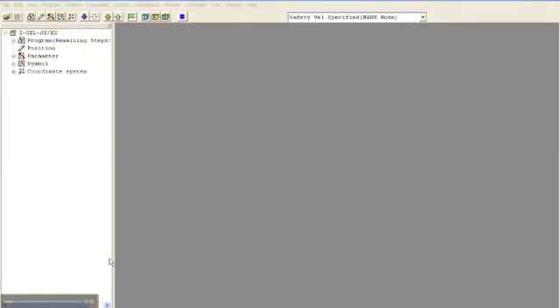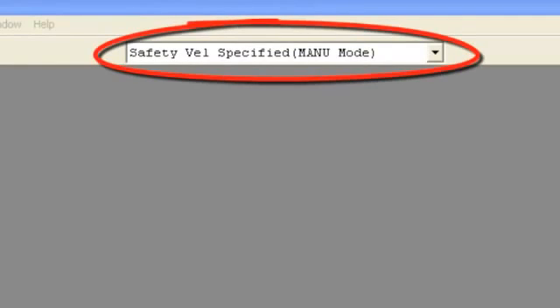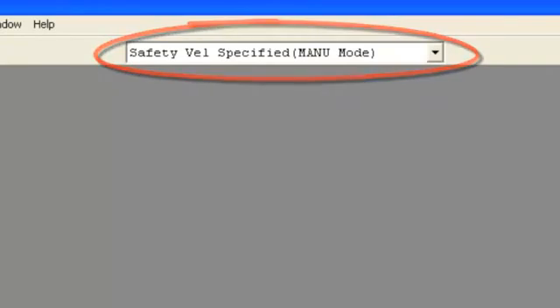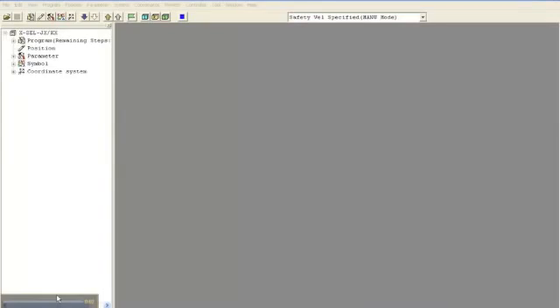The X-SEL software is program-based. The position information is stored inside the position table and the programs will call or reference this position information. Symbols are used to name positions, programs, variables, etc. to make reading and troubleshooting programs very easy. At the top, you will see a safety speed drop-down menu. The safety speed is always defaulted as on. The safety speed is set inside the parameters and will limit the speed of your actuator to 250 millimeters per second. When testing programs, make sure to turn off this safety speed to see the actual program speed, as a faster program speed may alter the path of your robot.